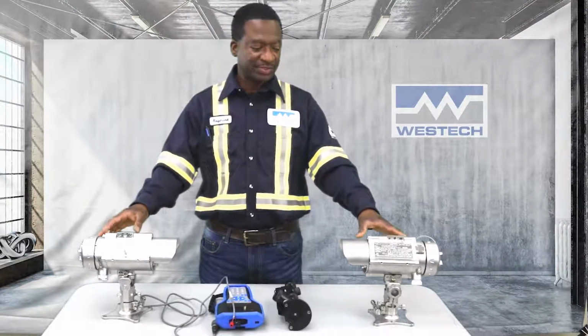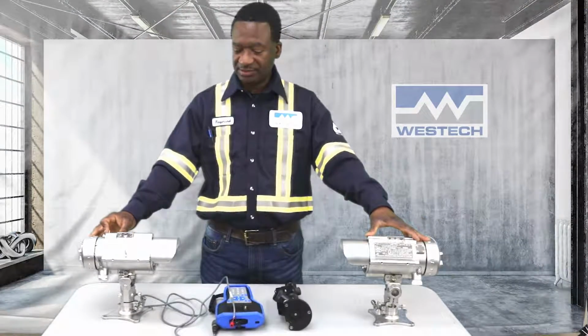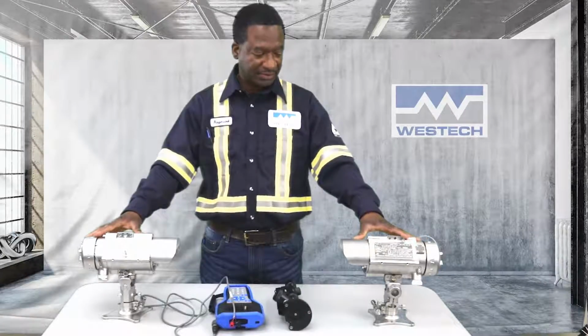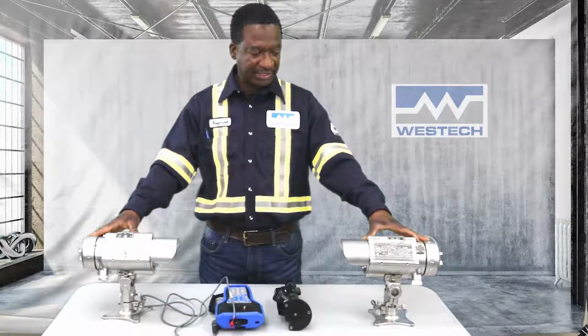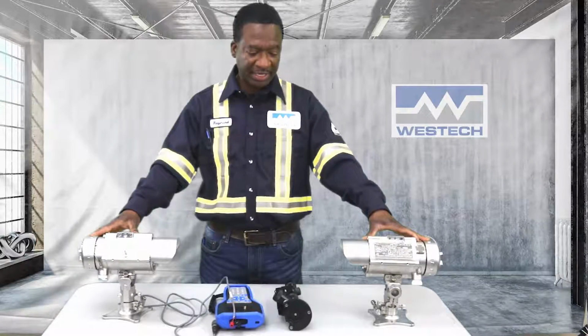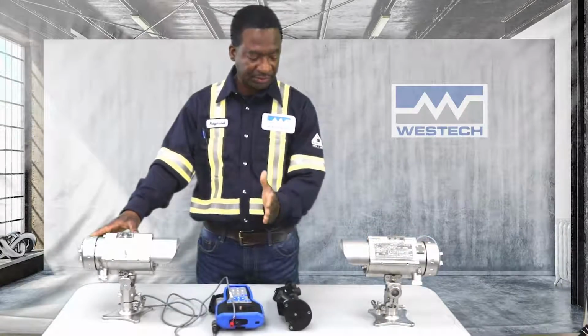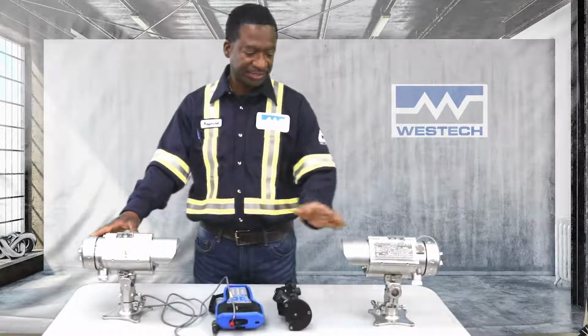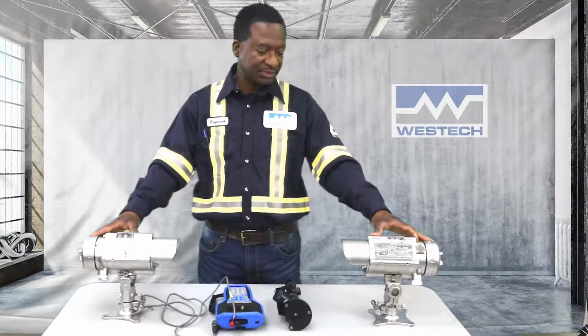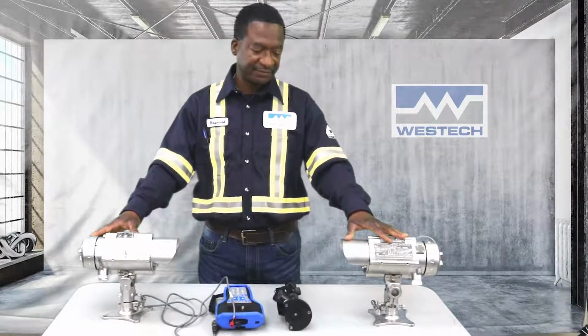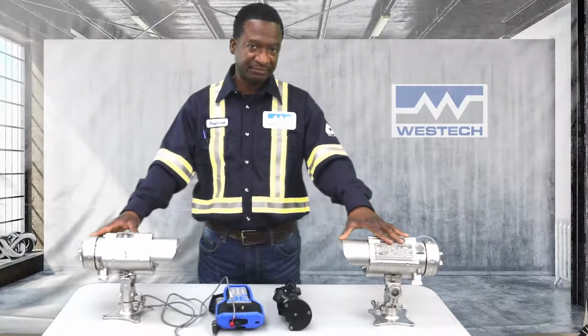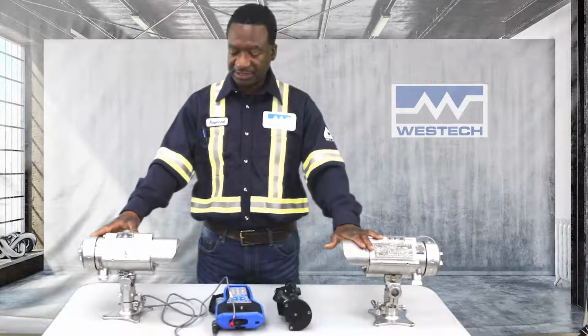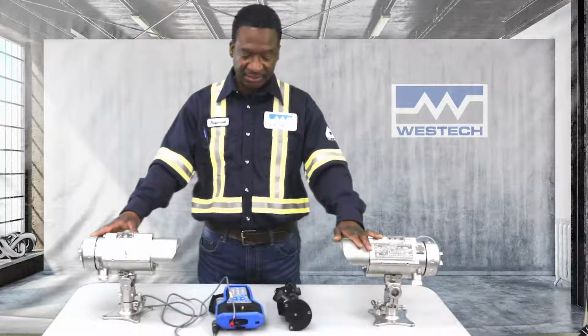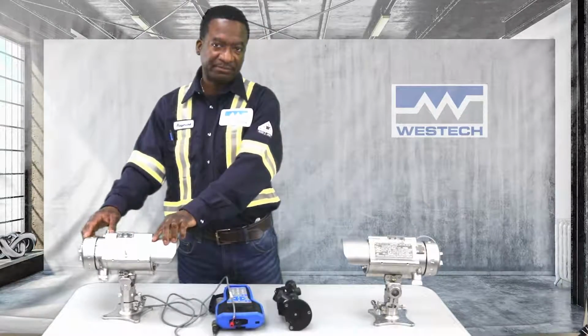The detection system consists of a transmitter and a receiver. The entire system is a line of sight system whereby there should be no obstructions between the transmitter and the receiver. The system generates an infrared beam for the LEL and a UV beam for the H2S. The receiver picks it up.